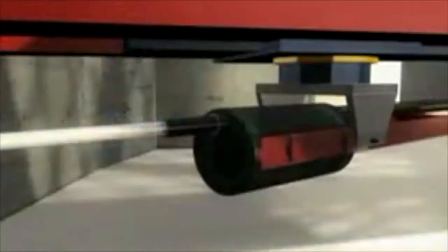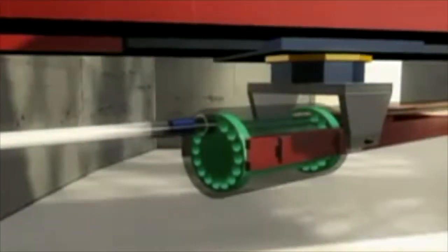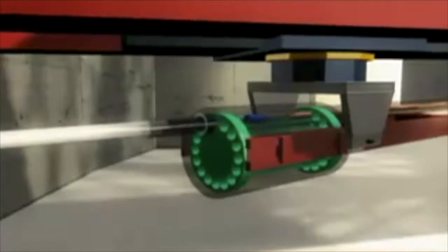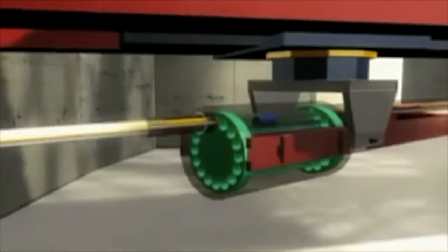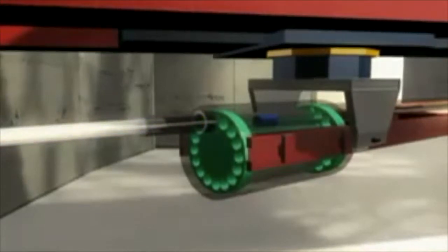Inside the containment, a fueling machine is aligned and clamped on to the new fuel port. The fueling machine snout plug is removed and stored. With the containment boundary maintained, the transfer ram pushes up to 16 new fuel bundles, one pair at a time, into the fueling machine magazine.